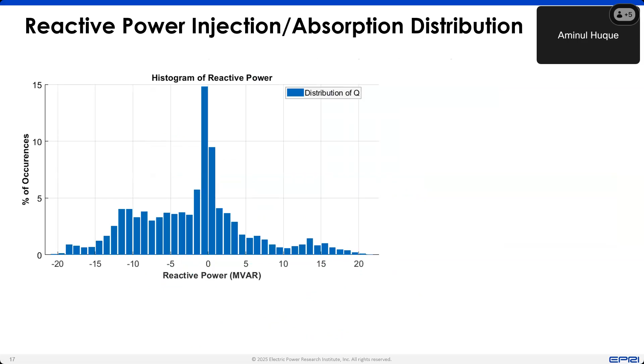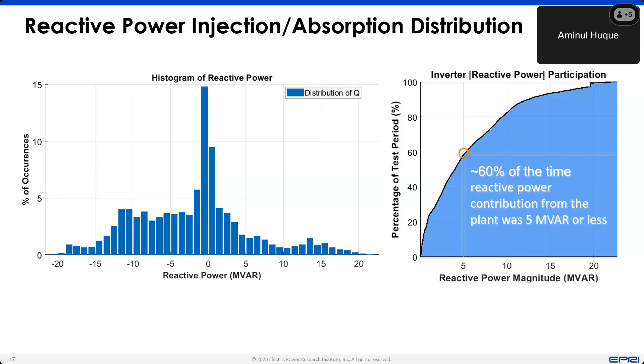And you're seeing the distribution of how much reactive power is actually absorbed or injected by the plant. Is it always 30 MVAR or 20 plus MVAR? Our conclusion is that almost 60% of the time, the reactive power demand was less than 5 MVAR. Remember that during the dead band there is no reactive power absorption or injection; it only acts when voltage goes outside the dead band, whether high or low. Over this test period, roughly 22 days, 60% of the time it was below 5 MVAR. But on a few occasions it went all the way to 24 or 25 MVAR, and this particular plant has a limit of 30 MVAR. Is that a technical limitation or a contractual limitation?